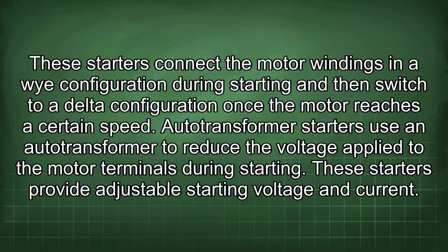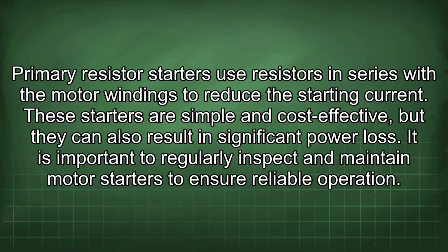Autotransformer starters use an autotransformer to reduce the voltage applied to the motor terminals during starting. These starters provide adjustable starting voltage and current. Primary resistor starters use resistors in series with the motor windings to reduce the starting current. These starters are simple and cost-effective, but they can also result in significant power loss.